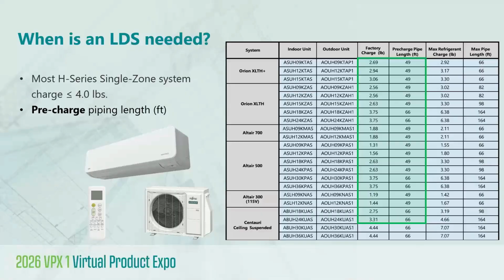A quick shout out here to our senior applied systems engineer, Mr. Leonard Stahl, who created these and many other helpful tables for you to use, including our 3C charge compliance calculator. Again, that's within Access. As a reminder, under the ASHRAE guidelines, systems with 4 pounds or less are automatically compliant. So you'll notice in the green columns that nearly all of our single zone systems fall below that 4 pound threshold, at least up to the refrigerant pre-charge length for the piping.